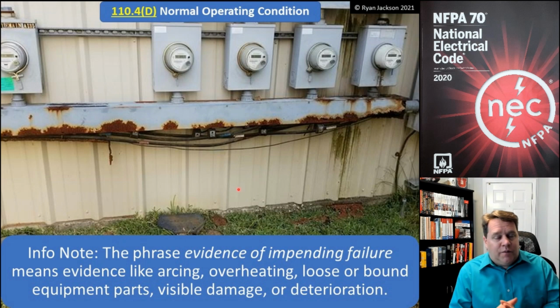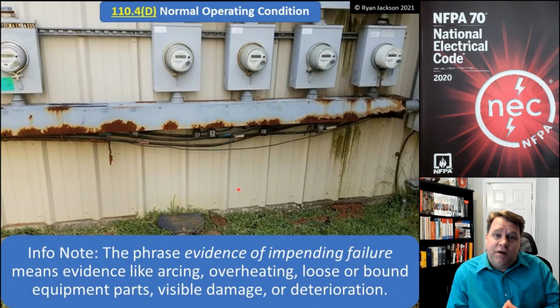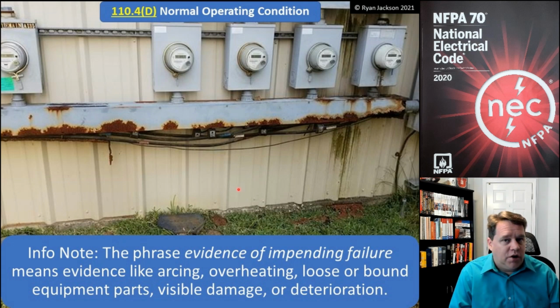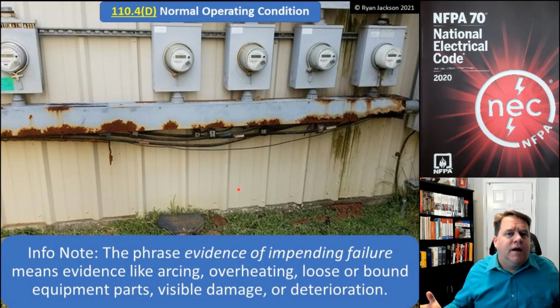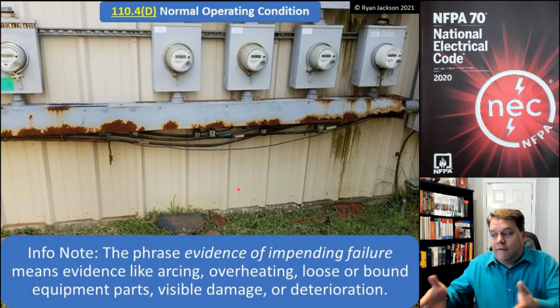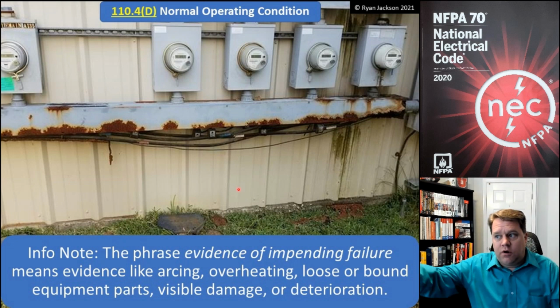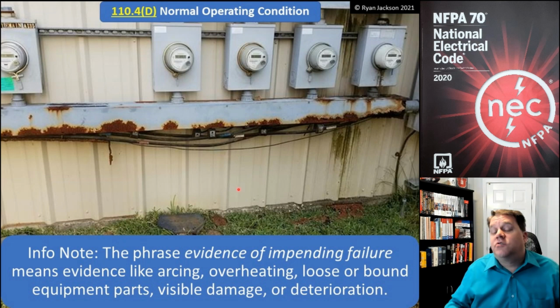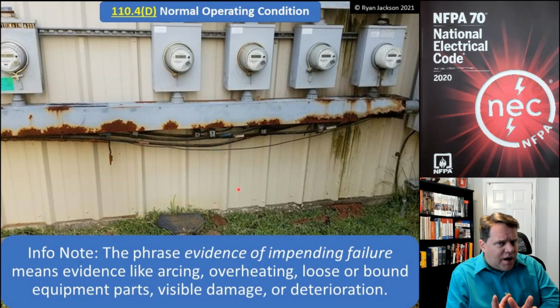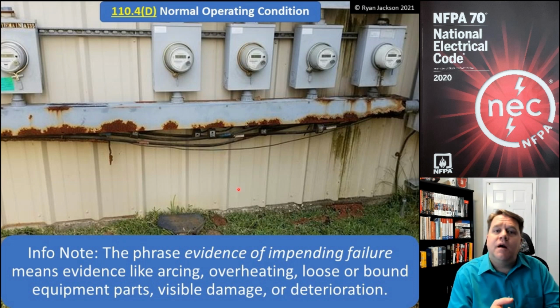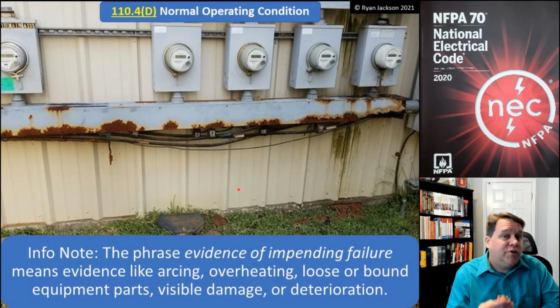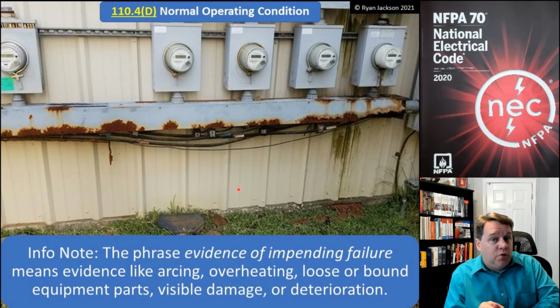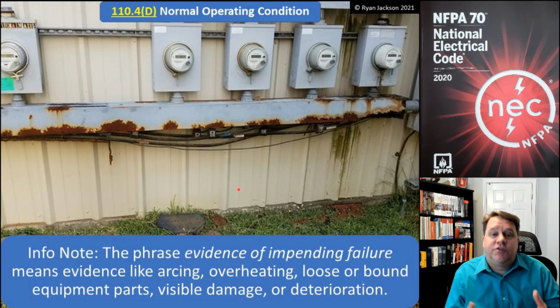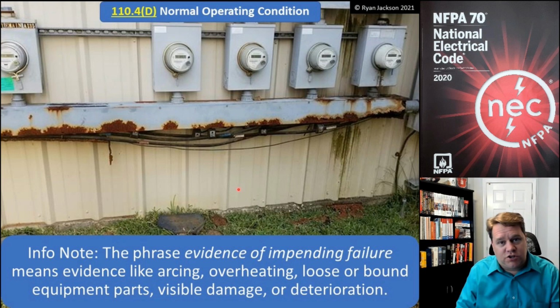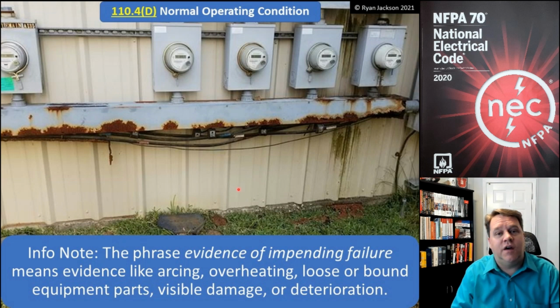But if your equipment is in a normal operating condition, you can perform normal operation of equipment. So you don't have to shut off everything in order to do every single thing that an electrician might have to do. Turning on and off a breaker in a normally installed piece of equipment is okay. So, when again do we have to have an electrically safe work condition? If I'm in the limited approach boundary, which is 3.5 feet for voltages up to 750, or if I'm doing something that's an increased risk of electrical injury. If I'm doing either of those two things, then I need to have it shut off, and more specifically, I need to have an electrically safe work condition.